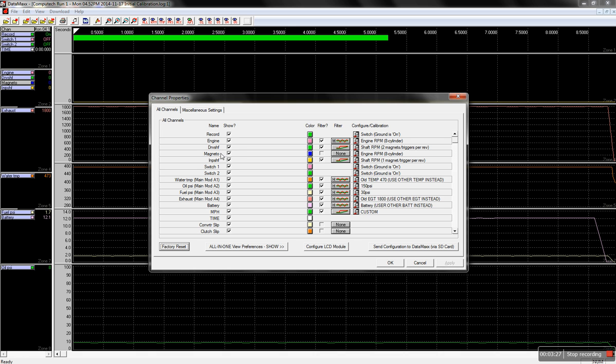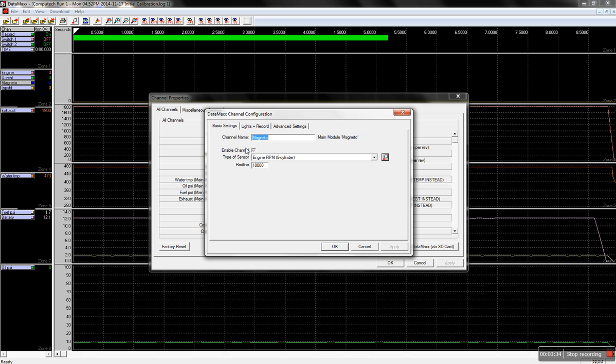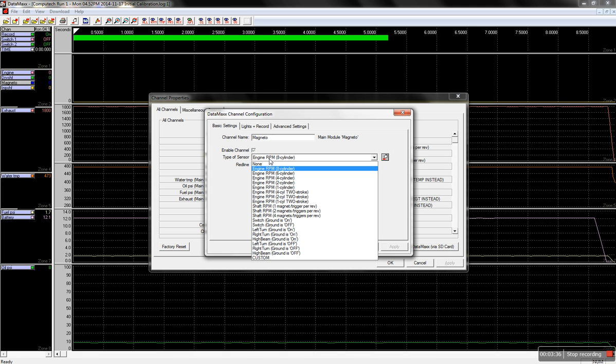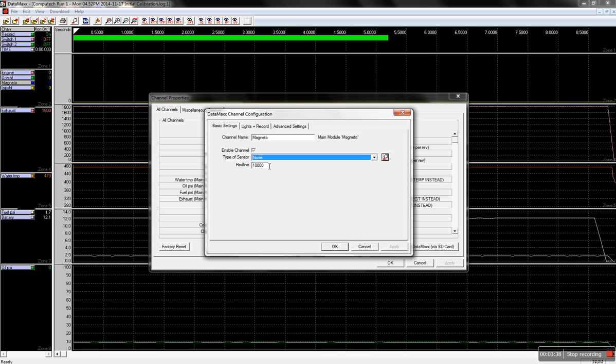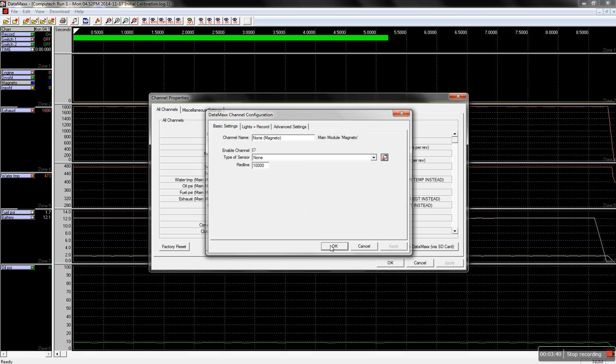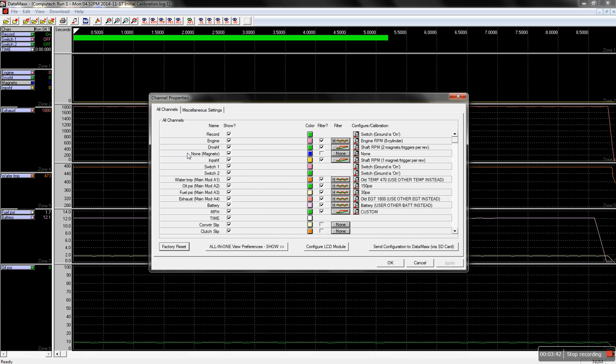To do this, follow the magneto line all the way to the right and click on the calibration button, which looks like a finger pushing a red button. You now have an option for type of sensor. We're going to select none from the top of the type of sensor drop-down list and hit OK. And you can see we now have none for the channel name of magneto.